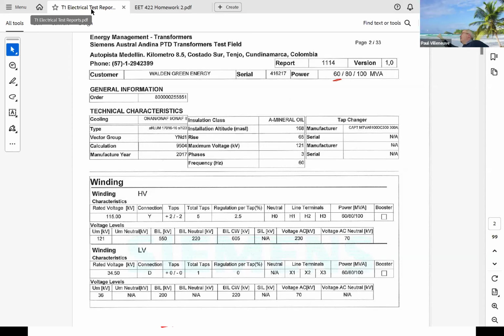So the reason why it has 60 is what's called its base rating. 60 is what it can do if it's just at ambient, and the ambient temperature is like 90 degrees. That's how much MVA you can run through it before you can start causing problems. To go up to 80, you've got fans with radiators on the outside, and the fans are moving air. So you're not just getting convection or conduction cooling, you're actually getting forced air cooling across the fans, and that cools the oil much more. So you can run it to 80 MVA. 100 MVA means you've turned on your second stage of fans.